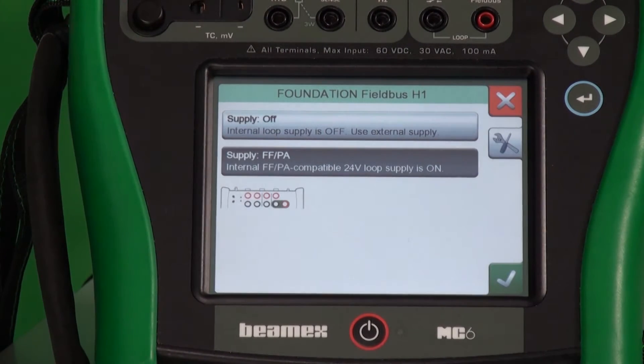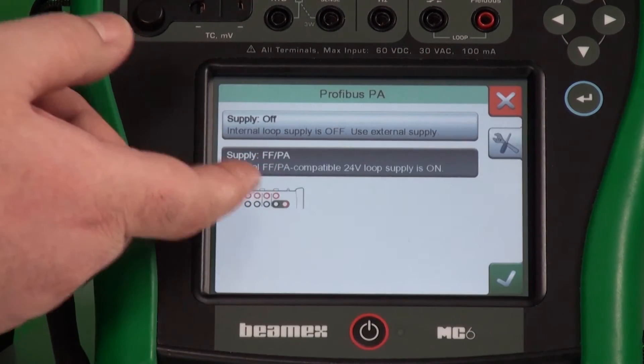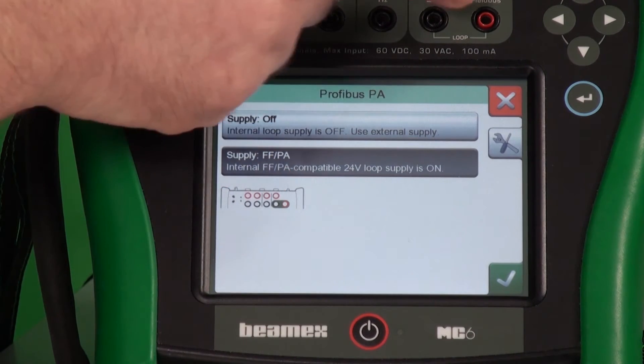Also, Foundation Fieldbus — it's the same thing, the same two connections. You decide whether or not you have loop power. One thing I didn't mention with HART is that we build in the 250 ohm resistor for that communication. In Foundation Fieldbus, it's a 50 ohm resistor. So by using supply on, we automatically put that in. If we go back to Profibus, same thing — Profibus also uses a 50 ohm resistance. Supply on, same two connections.